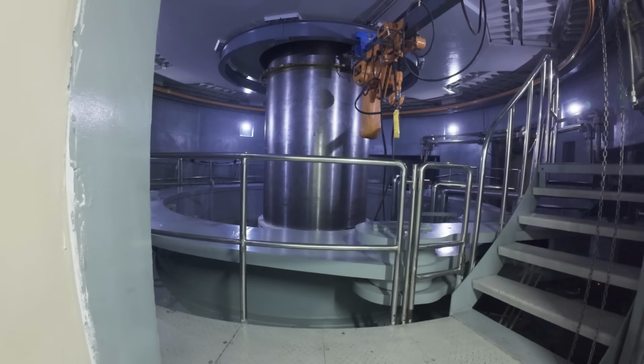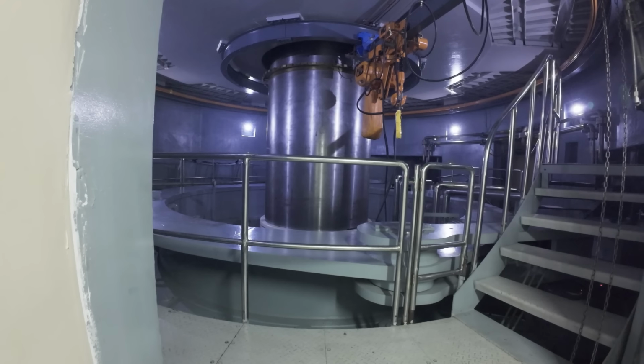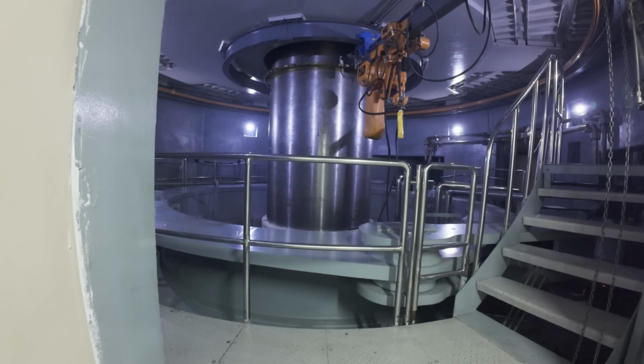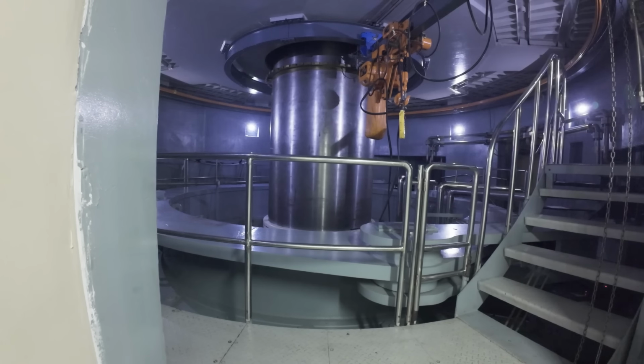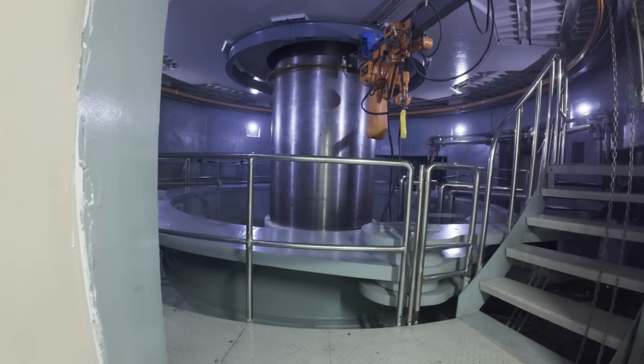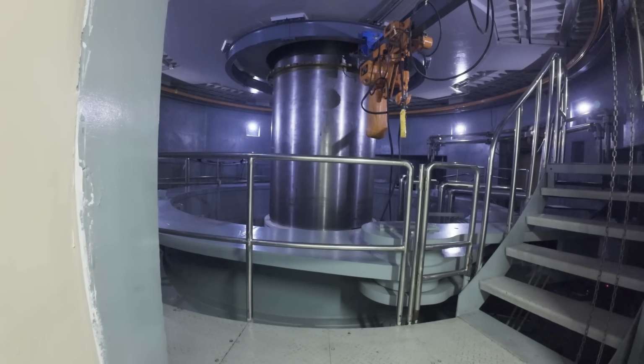After this, then comes step number 6. Remove turbine auto lock. During the shutdown, mechanical locking pins, hydraulic brakes, and parking device keep the turbine shaft secured against unintended movement. Now these protections are removed. This is the moment the turbine generator transforms from a static mechanical structure into an active rotating machine. And once this lock is disengaged, the next step becomes impossible to ignore.